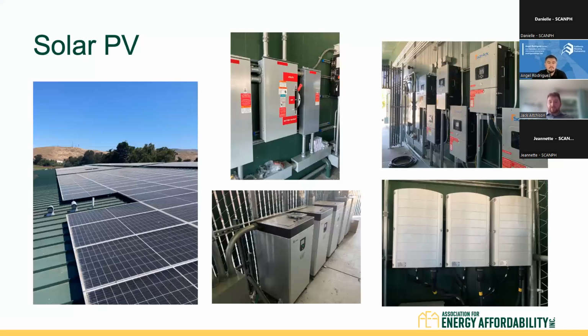So there are lots of components of solar PV systems. You have your panels themselves. You have all of your electrical gear. You potentially have batteries. You have inverters for the solar. You have inverters for the batteries. There's a lot of electrical components here associated with solar PV. Fortunately, most of this stuff is going to be contained within the box and should not need to be replaced, and you shouldn't have to maintain any of this equipment. However, the key to maintaining a solar PV system is monitoring for issues.